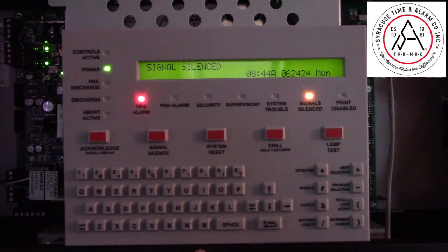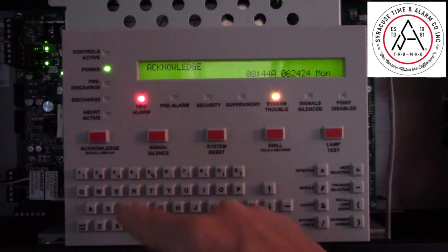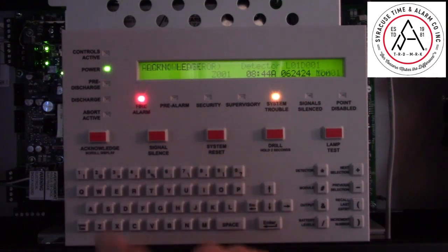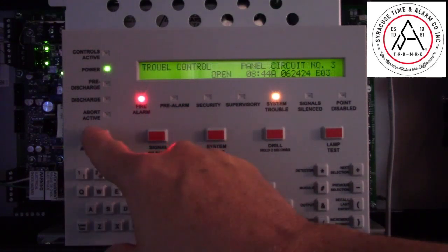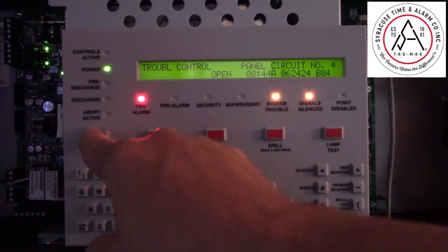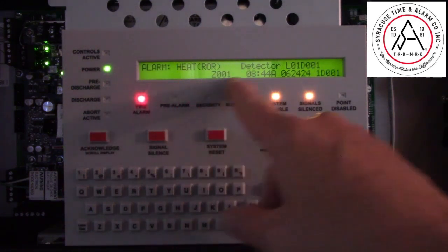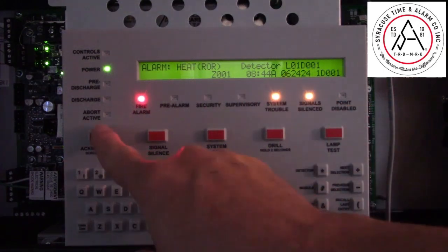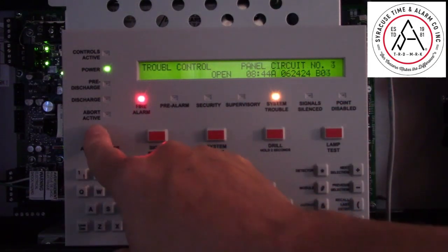Once it's silenced, now you can scroll through the alarms and the troubles. So we see we have one alarm on a heat detector and our two bell circuit troubles.